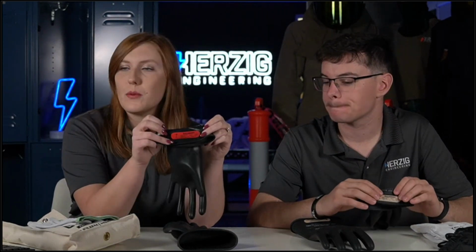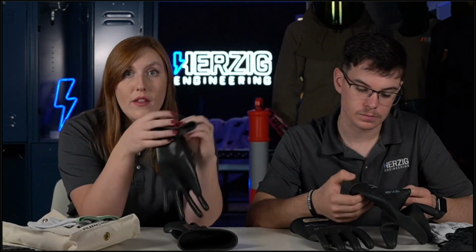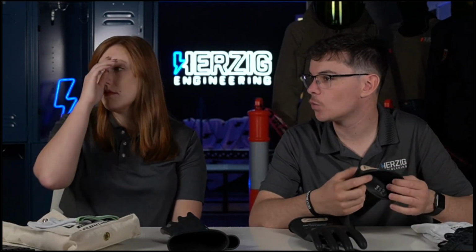And you've got the red tags, right? I've got the beige. So I've got the double aught gloves. It makes it really easy to tell the difference between the ratings. The red tag means that I have gloves that, if they were within the test range, are good up to 1,000 volts AC. So if I was working on a system that had a wild leg or something that spiked over 500 volts from time to time, then I would want the Class 0 gloves. Most people who have 480 volts or less only need the double aught, the beige label that Trey has. That's nice. The gloves say what they're rated for, what they can be used on. We probably know the colors off the top of our head, but the gloves will say which voltage they can be used on themselves.